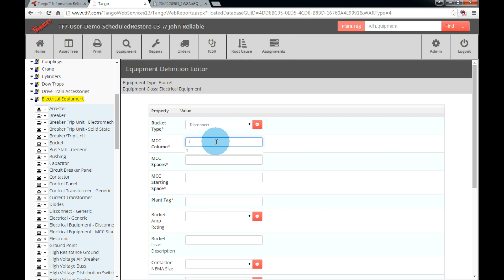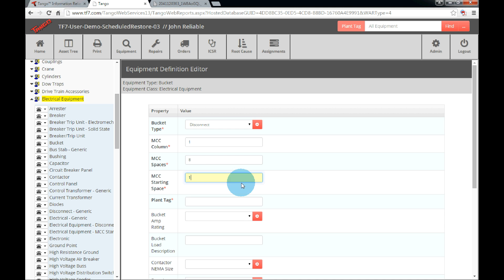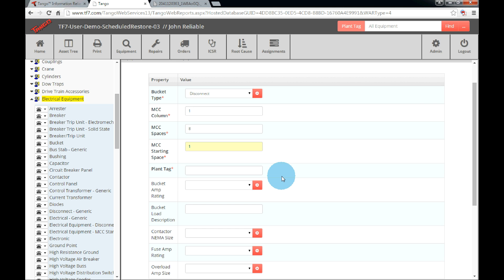MCC Spaces is asking how many spaces does the bucket occupy. In this example, the first bucket takes up 8 of our 18 spaces. MCC's starting space means which space does the bucket start. The first bucket in a column will start in space 1. However, if this is the second bucket we are adding and the first bucket takes up 8 spaces, then our starting space for the next bucket would be 9.